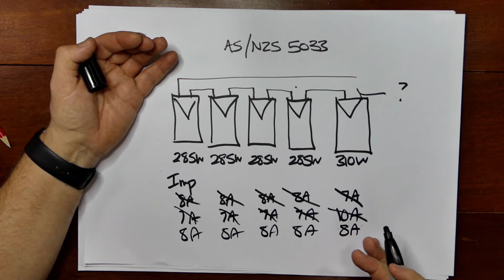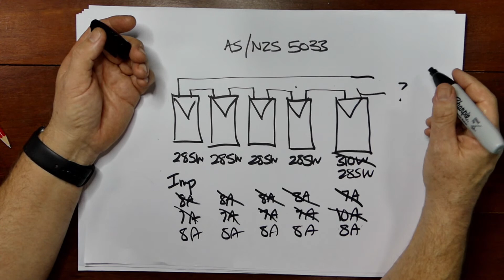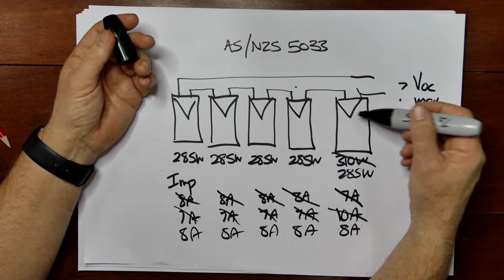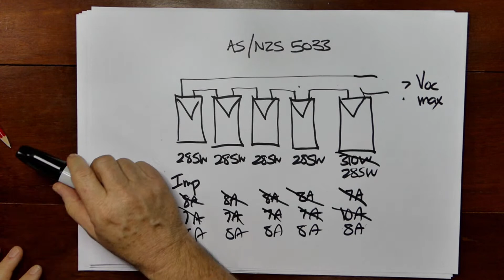So we don't actually get 310 watts out of it, but it's still fine. There is one more consideration: are you exceeding the maximum voltage of the equipment? What is the voltage open circuit max? Now you've added one more panel in the string, so the voltage will have gone up by the addition of that panel. Make sure that's not exceeding the rating of the product you're installing and connecting it to. So hopefully, Chris, I answered your question there.